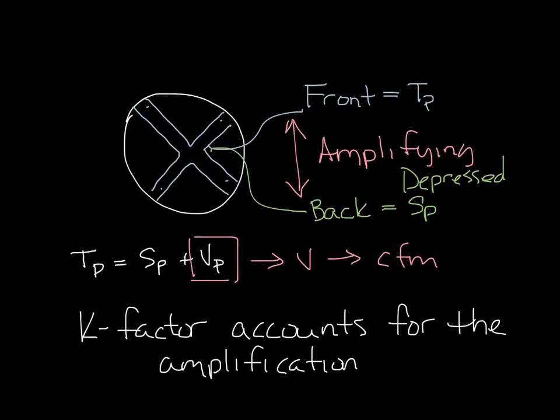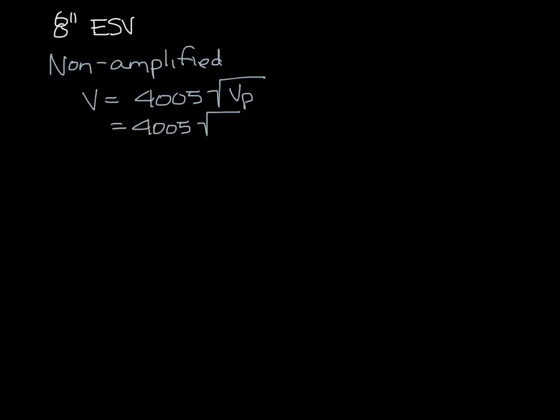Let's look at how this works and why it's a good thing. Let's say you have an 8-inch ESV. Let's calculate the lowest CFM the pressure transducer can read from a non-amplified signal and from an amplified one. First, the non-amplified signal. We know that the pressure transducer wants 0.03 inches, so let's convert that to a velocity. Velocity is equal to 4005 times the square root of the velocity pressure. So that's 4005 times the square root of 0.03, and that equals 693 feet per minute.